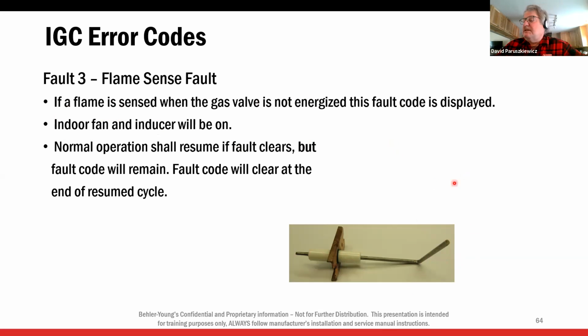So it means, yeah, at some point we sensed a flame when one shouldn't have been present. Maybe the gas valve stuck open, so we did have a flame. Okay, but the indoor fan and inducer will be on, because if the gas valve were to stick open, the flame would stay on. Of course, it would leave the blower running, so that we would at least not overheat the unit.